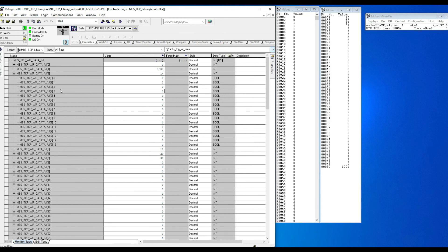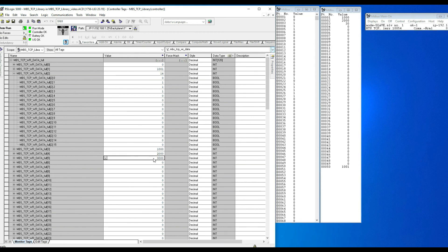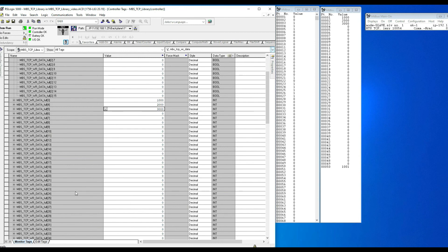Finally, we write to holding registers starting from element 3 in the write array. The MDBus holding registers currently show 10, 20, 30, and so forth. Setting the PLC write array to 1000 and 2000, we immediately see 1000 and 2000 appear in MDBus, followed by 3000, and so on all the way through. Writing 150 into the last register shows 150 in register 20 in MDBus.